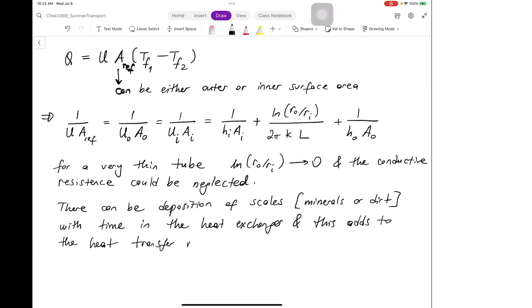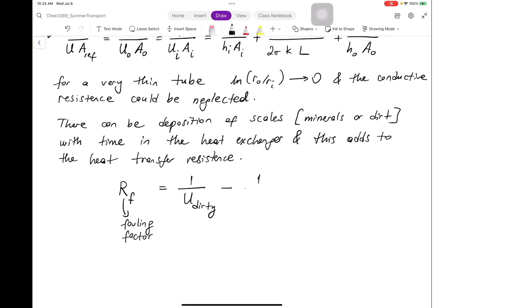A good way to model this is to use what's called a fouling factor. We use R for resistance and F for fouling, so this is the fouling factor, equal to 1 over U dirty, the one with scaling layers, minus 1 over U clean. 1 over U clean corresponds to the original clean heat exchanger, but the dirty one should give a larger value. The difference between the two is the fouling factor, so you should add it or take it into account during your design.